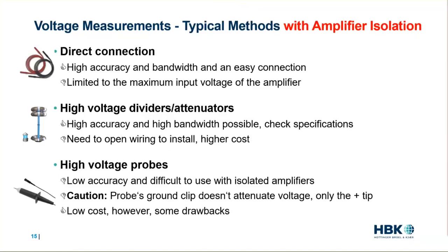Now, another method is through the use of high voltage dividers and attenuators. You can gain high accuracy and sometimes high bandwidth, but you'll need to check the specifications. Of course, you'll need to open the wiring to install a high voltage divider or attenuator, and they do come at a higher cost. High voltage probes offer low accuracy, and sometimes they're difficult to use with isolated amplifiers. And a note of caution, the probe's ground clip does not attenuate the voltage. The positive tip of the probe is the only part that actually attenuates the voltage. So be sure and keep that in mind. It's one of the drawbacks of voltage probes. Even though they come at a lower cost, they do have several drawbacks.